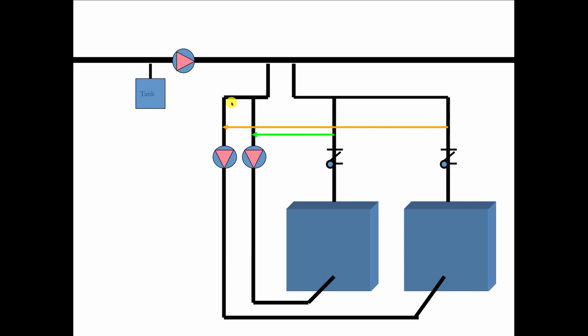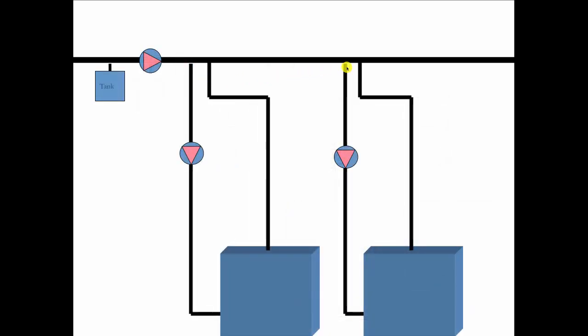Another way that it's done is like this, where we're hanging the boilers like curtains on a rod. This isn't as good because let's say this is looking for 180 degree water and this first boiler comes on and it brings the water from say 160 up to 175.